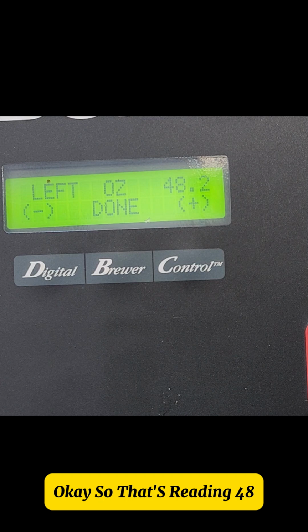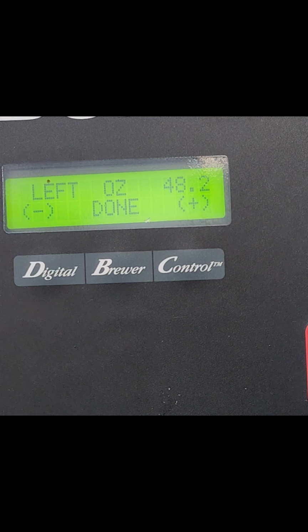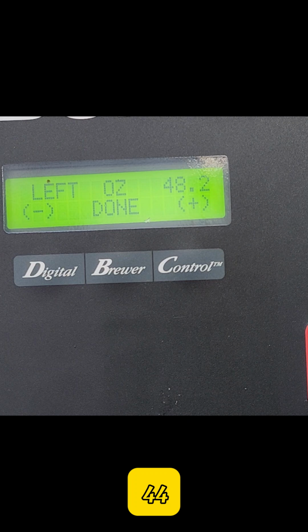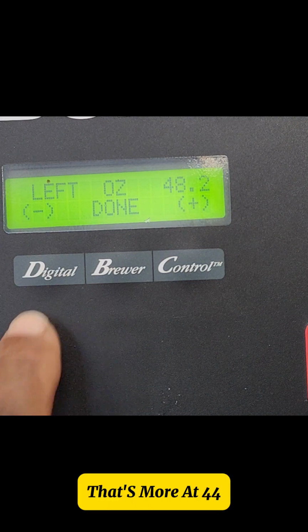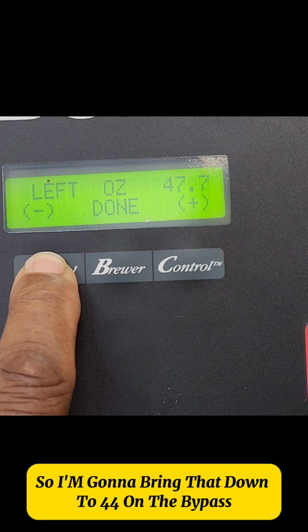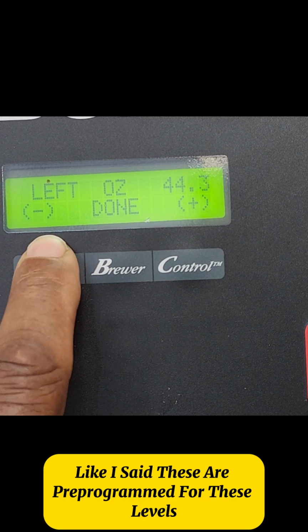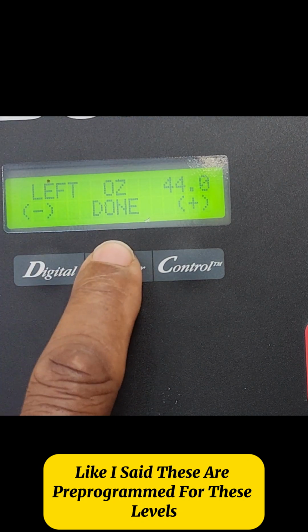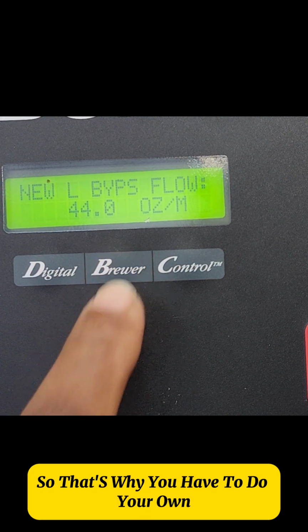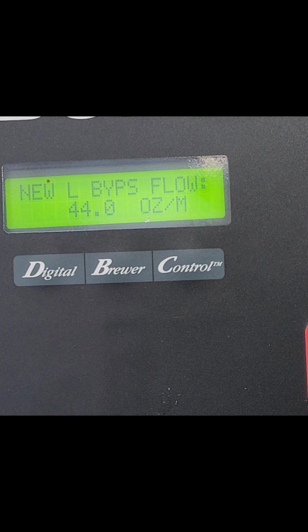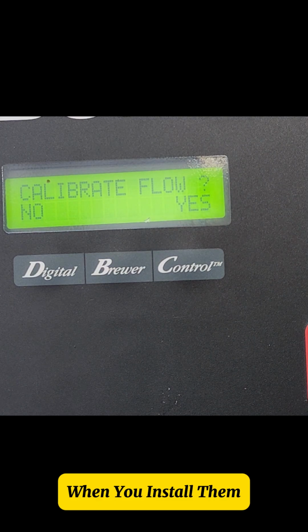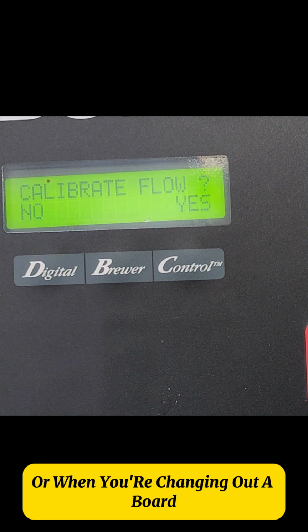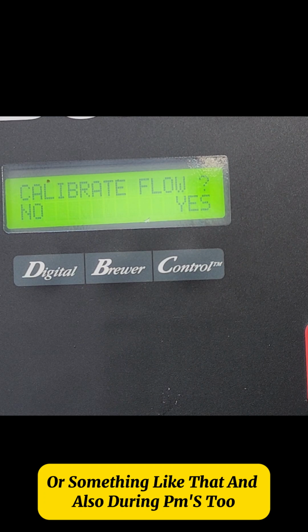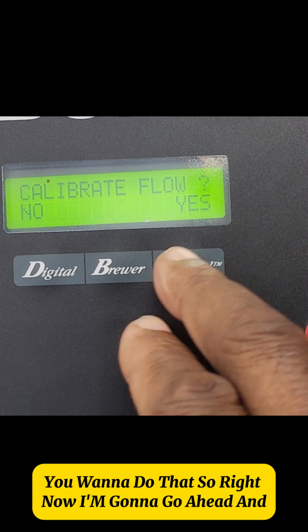Okay, so that's reading 48, 42, 44. That's more at 44, so I'm going to bring that down to 44 on the bypass. Like I said, these are pre-programmed for these levels, so that's why you have to do your own calibration on these machines when you install them, or when you're changing out a board or something like that.